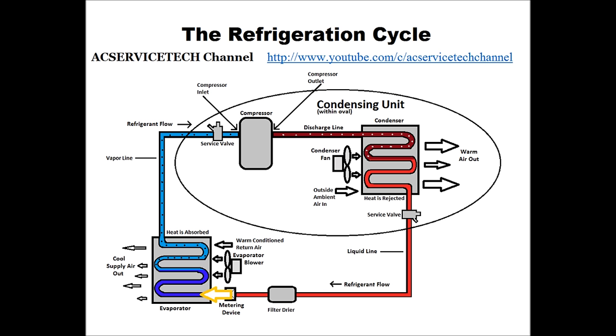After that, in the evaporator coil, as it absorbs heat, it turns into a saturated state in the middle of the evaporator coil. After it turns into a complete vapor, right after the saturated state, from where it turns into a vapor to where it comes out of the evaporator coil — that's called the superheat. It's the temperature increase in vapor form. It then proceeds into the compressor as a low pressure, low temperature vapor, and the process starts all over.